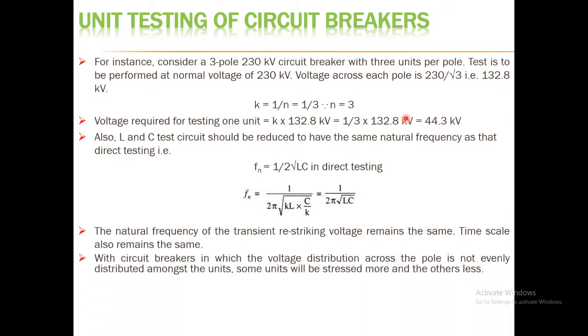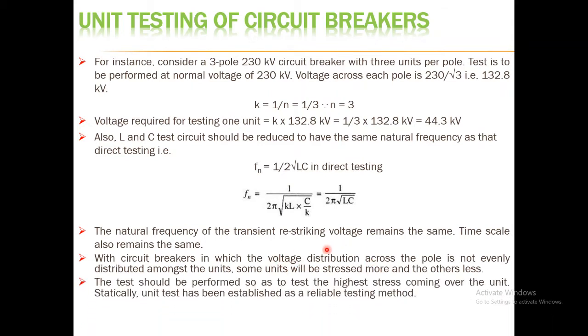With circuit breakers in which the voltage distribution across the pole is not evenly distributed among the units, some units will be stressed more and others less. In such cases where voltage distribution is not uniform, the test should be performed so as to test the unit experiencing the highest stress. Statically, the unit test has been established as a reliable testing method.